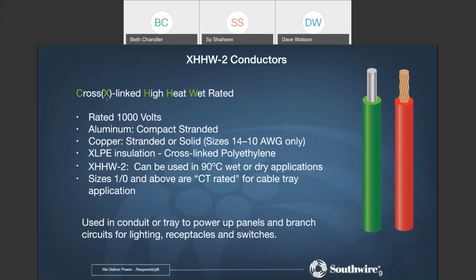The OD is going to be very similar in a number of sizes to the THHN. Some of them are going to be a little bit higher, a little larger. So yeah, the conduit fill will be a little bit higher when you use these conductors. But these conductors, as I alluded to earlier, are going to have that cross-linking in between the polymer chains. Therefore, they're going to be a bit more rugged, and so you should sustain less damage to your conductor insulation during the installation process.